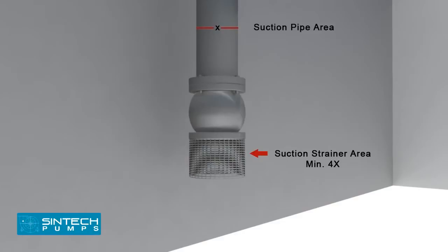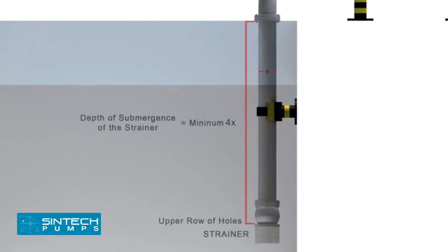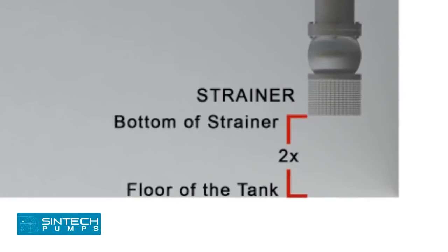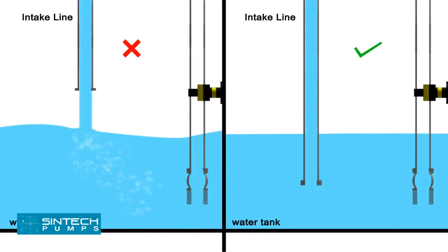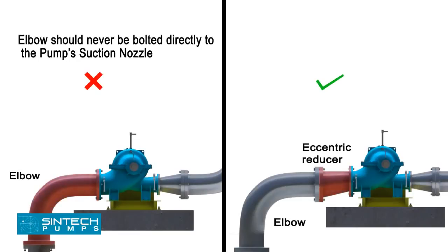The suction strainer must be at least four times the suction pipe area, and the mesh should screen out solid particles that could clog the impeller. The minimum depth of submergence of the strainer should be at least four times the pipe diameter, measured from the upper row of holes of the strainer. The distance between the bottom of the strainer and the floor of the tank should be two times the pipe diameter. A stream of liquid falling into the tank near the intake pipe will draw air into the liquid; the supply line should extend down into the liquid.